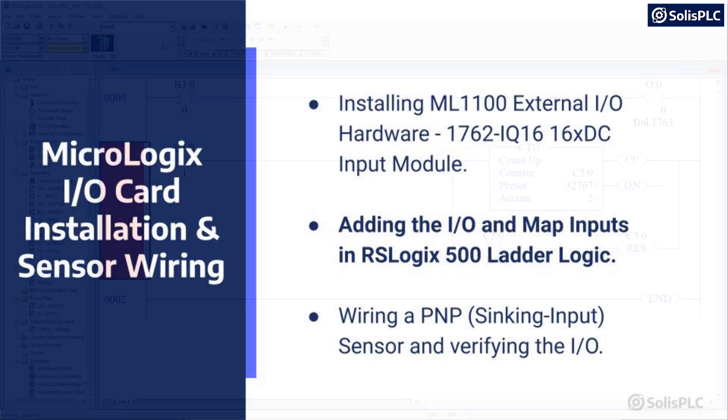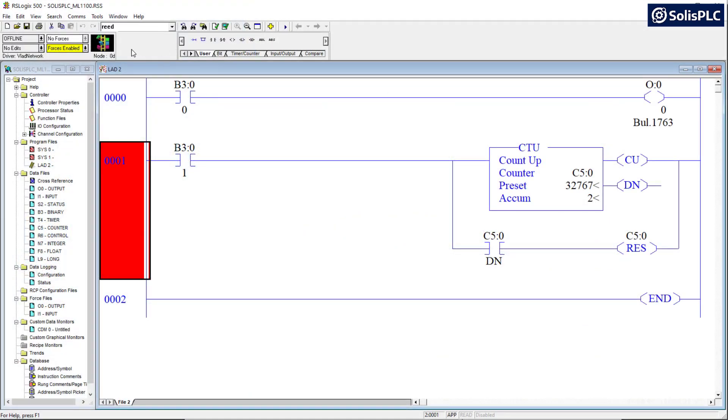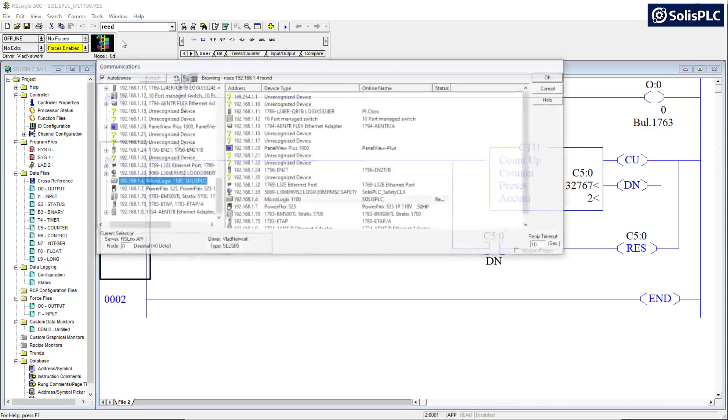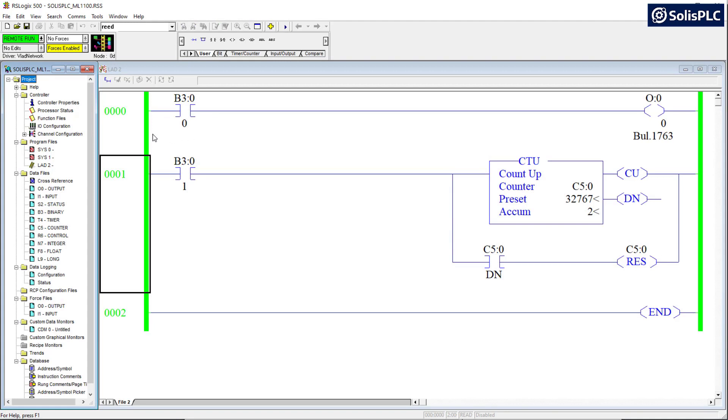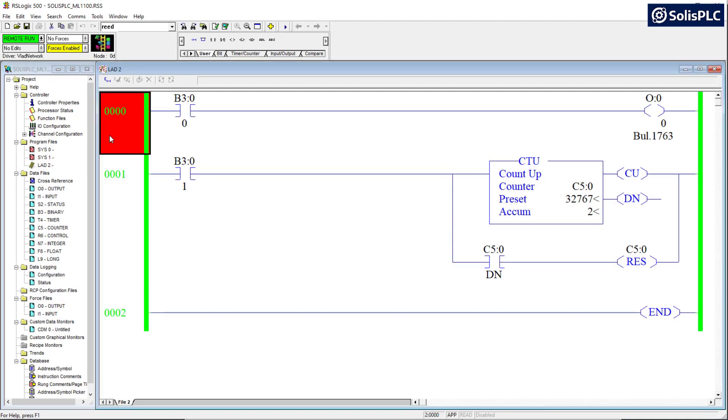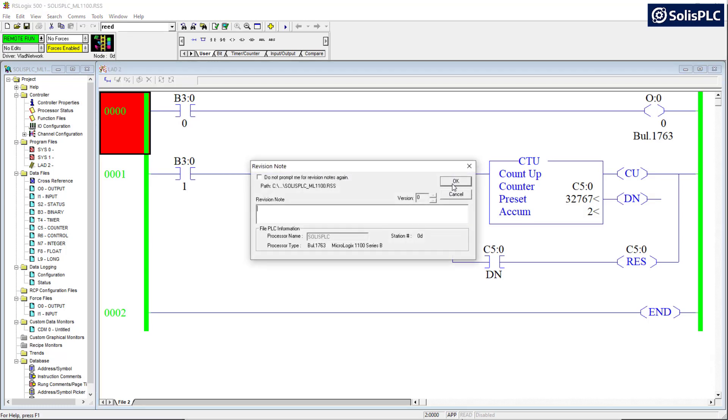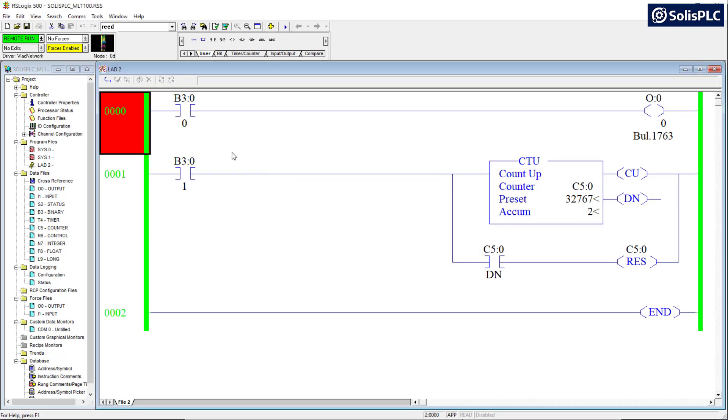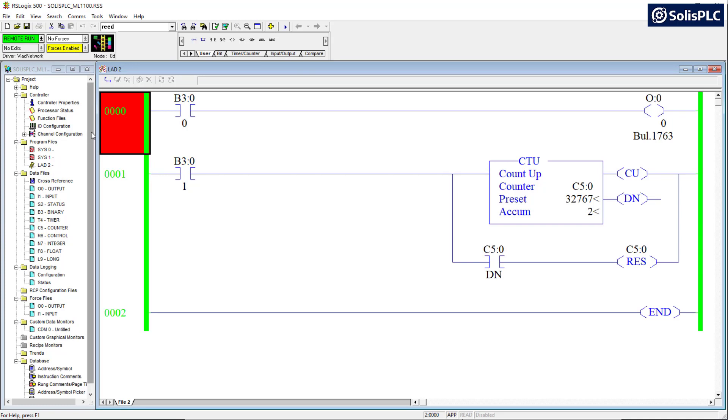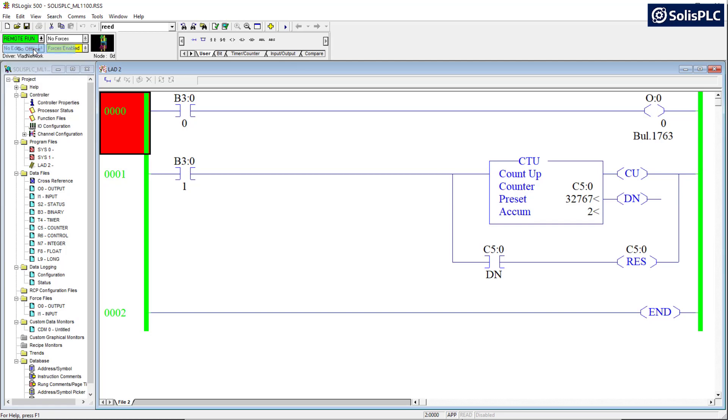Okay, so here we are in RSLogix 500 with the latest program that I had on my desktop. The first thing that I always recommend before we're going to add the I/O card is to go online with the PLC and perform a comparison with the current code. So I'm going to enter comms, who active, and then select the MicroLogix PLC in this I/O tree. Press OK. And we should be able to go online. As you can see, we are in remote run. What I'm going to do is save my program by clicking the save button. Press OK. I do want to upload all the values. The reason for this is because in a typical plant environment, things may have been changed by somebody other than you, and the latest program is going to be backed up this way because we will be performing a download.